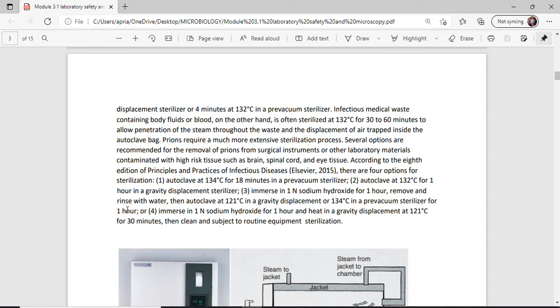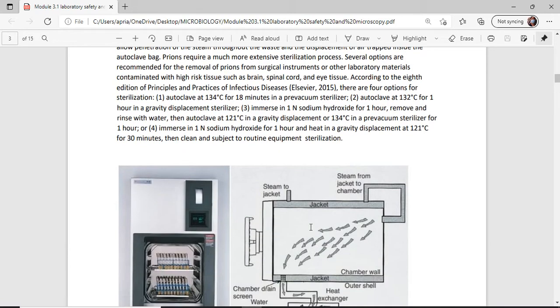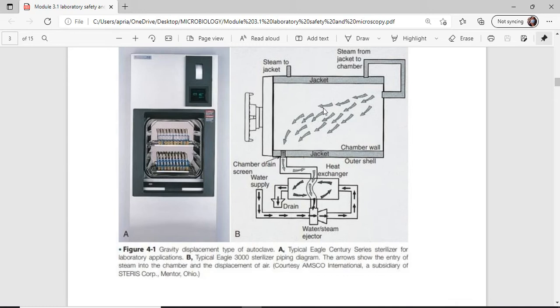Or, the fourth of the four options: immerse in a 1 normal sodium hydroxide again for 1 hour, then heat in a gravity displacement sterilizer at 121 degrees Celsius for 30 minutes, then clean and subject to routine equipment sterilization. You have here an illustration, a picture of the autoclave.